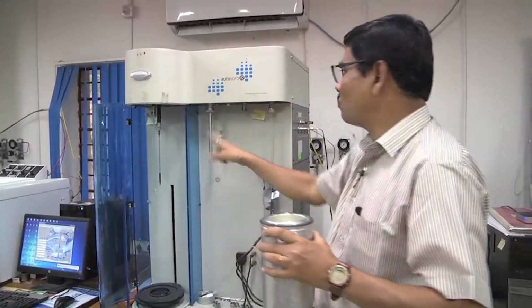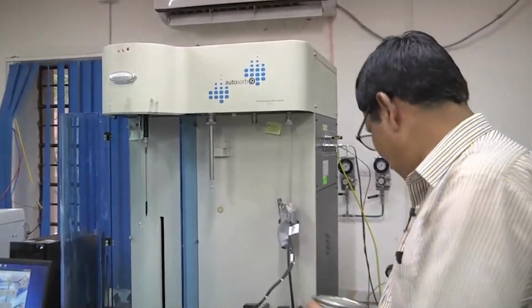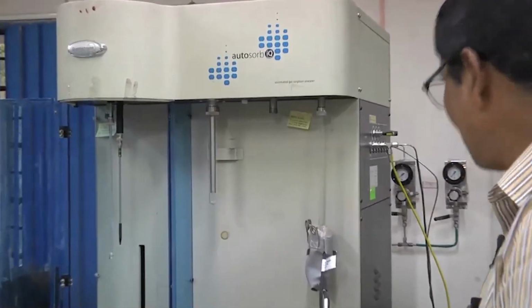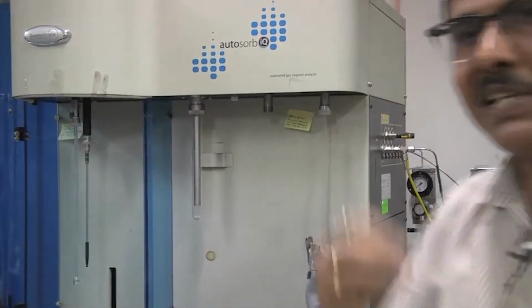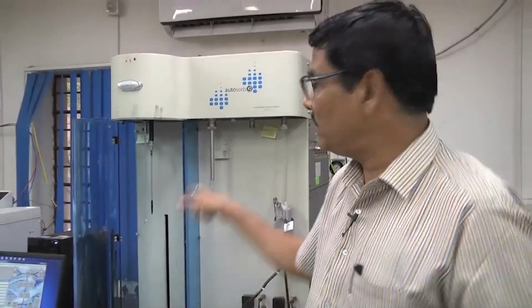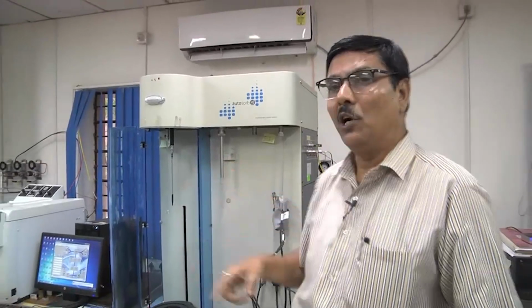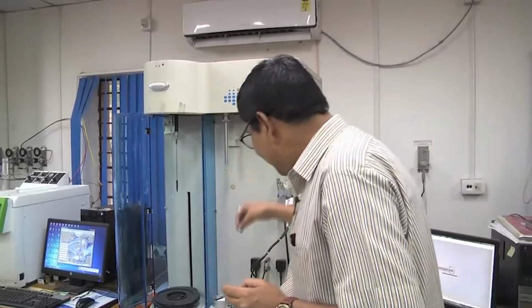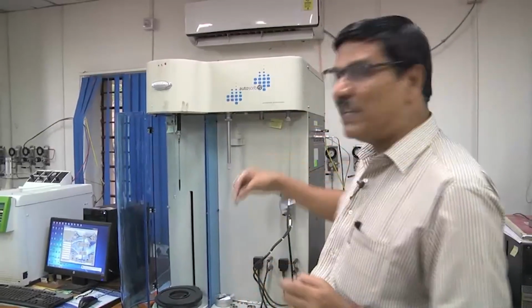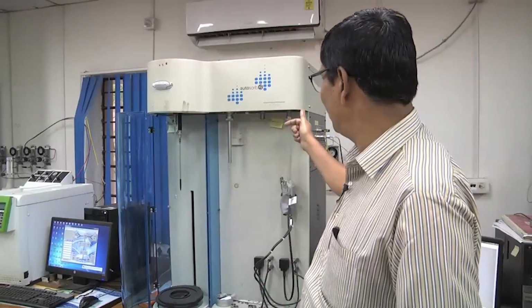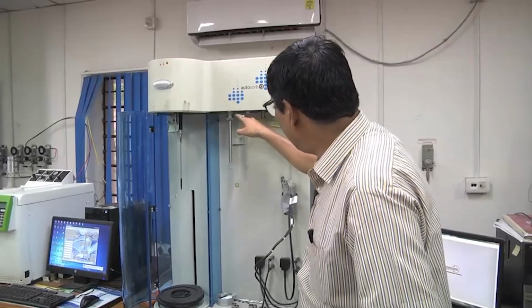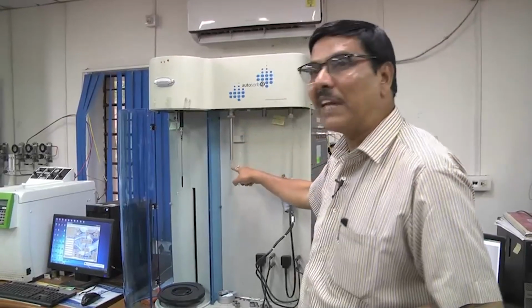This section is called cold trap. Now, what is the function of this cold trap? While degassing, some moisture or volatile matter is coming out, and there are two pumps inside this instrument. One is called the dry vacuum pump and another one is called the turbomolecular vacuum pump. From that side also, if any oil or spillage comes to this section, then this will go directly to this cold trap.